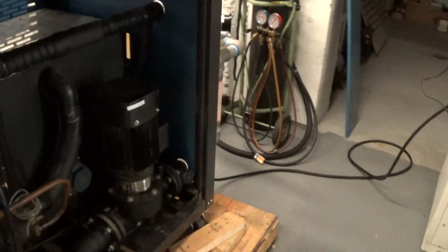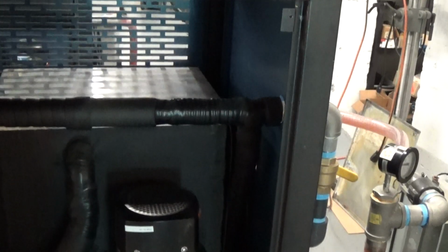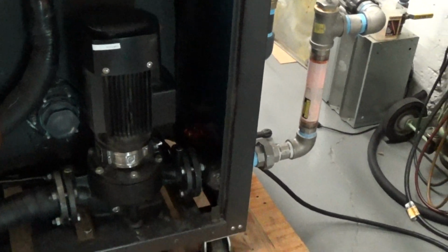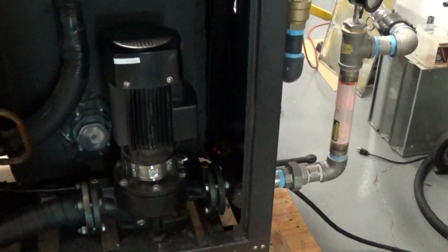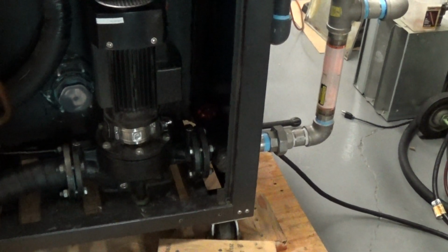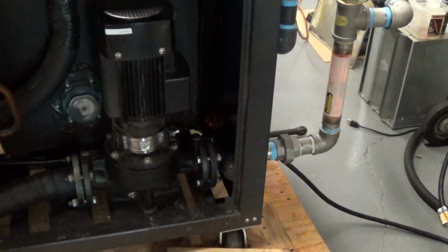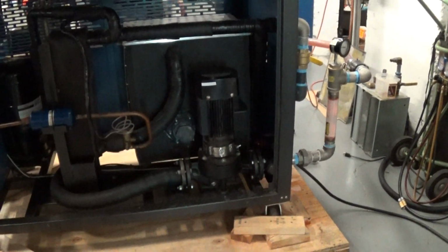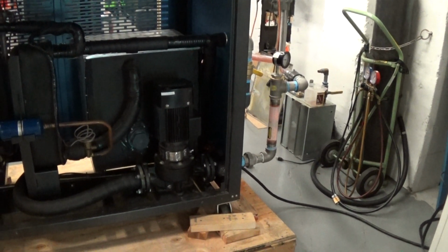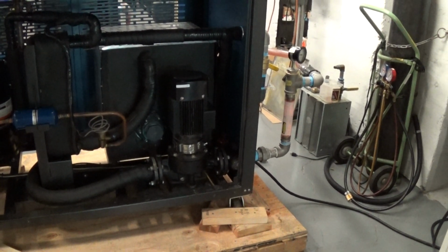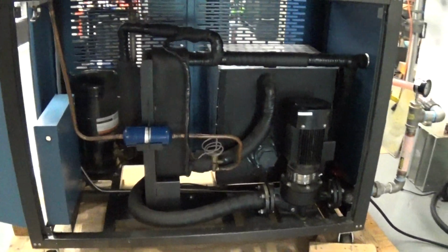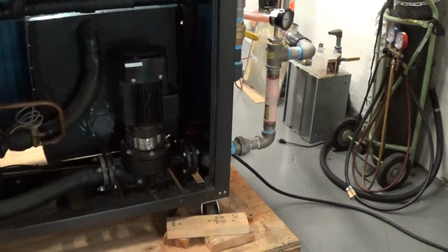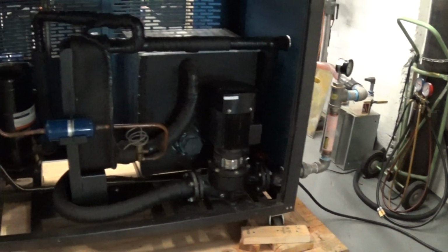The unit does have its own internal adjustable manual flow bypass. You can see that basically looks like a boiler drain knob that connects the supply to the return. We're going to ship that cracked open a turn or two. Unless you have a bypass in your loop, you should not have that fully closed. But in some cases, you may have to open that up a little bit. A symptom would be, if you're not bypassing enough and you have too much restriction on your process, that we're restricting too much flow back to the heat exchanger here, it would go into low pressure alarm, and that can be related to not enough flow, in which case we would open up that valve another half turn and see how it ran.